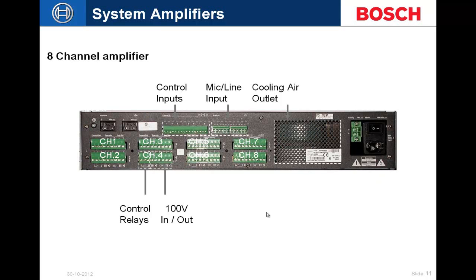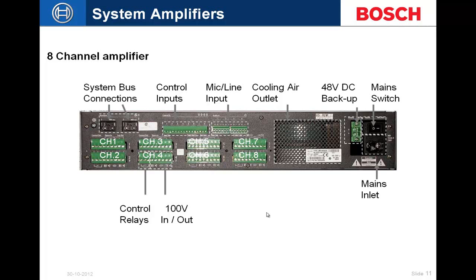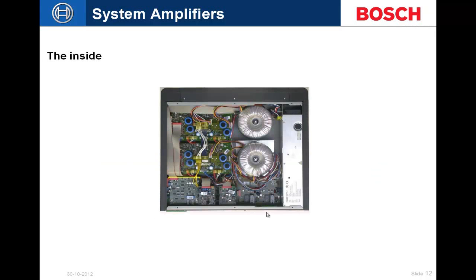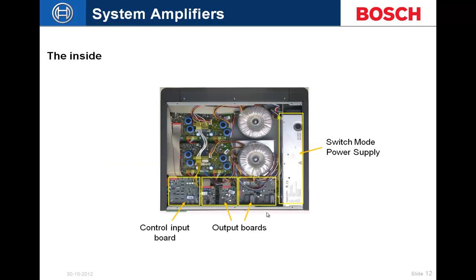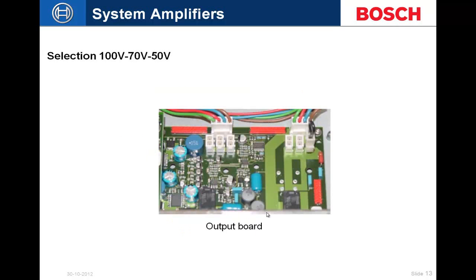The eight-channel amplifier rear has four line or mic inputs, 48-volt DC backup power, mains power, and two system bus connectors. Inside, there is a control board, power supply, output boards, output transformers, and class D power amplifiers. A jumper on the inside switches the output between 50, 70, and 100 volts.